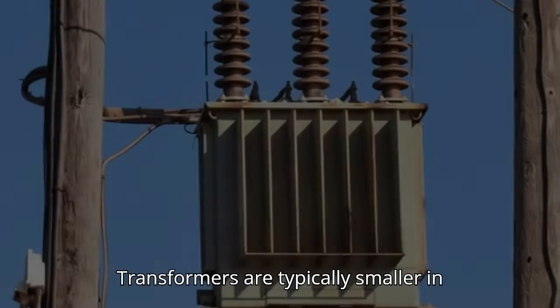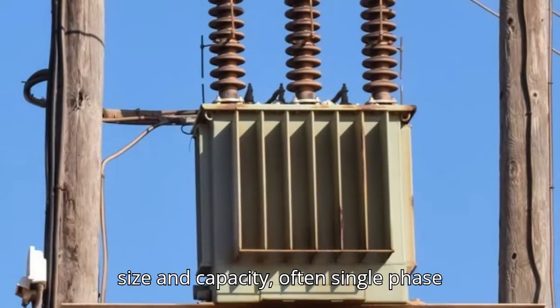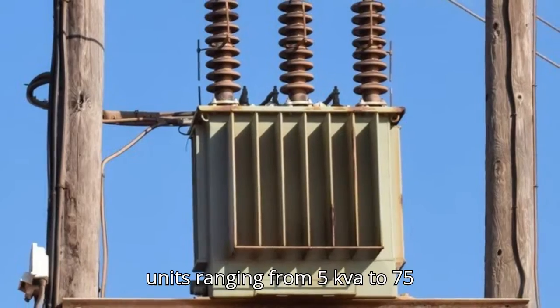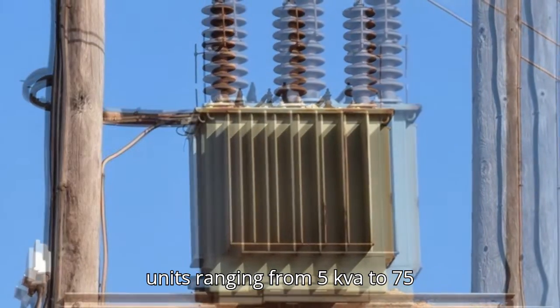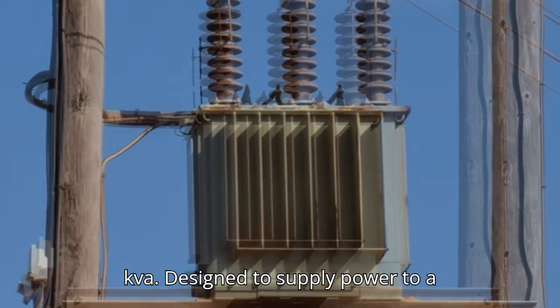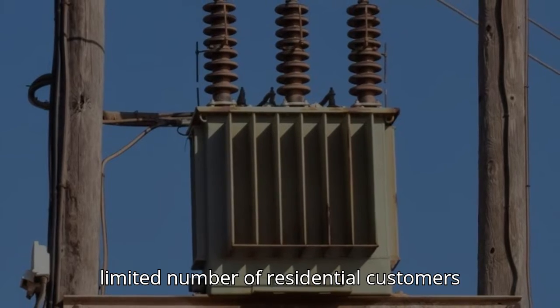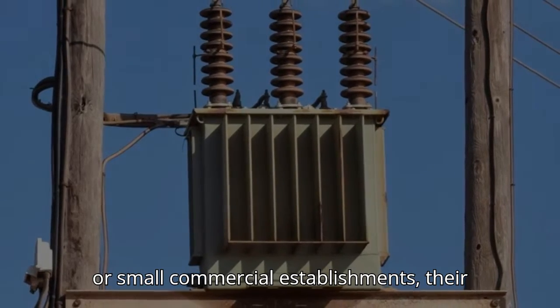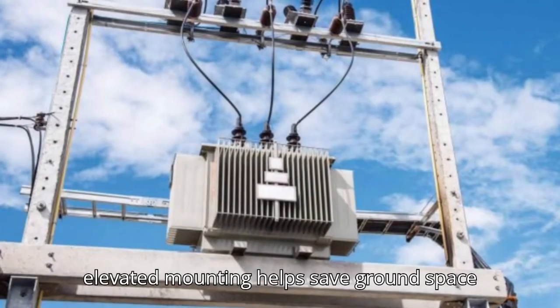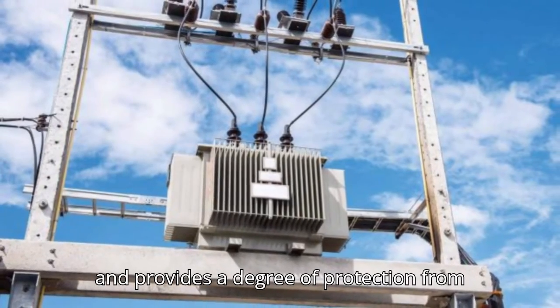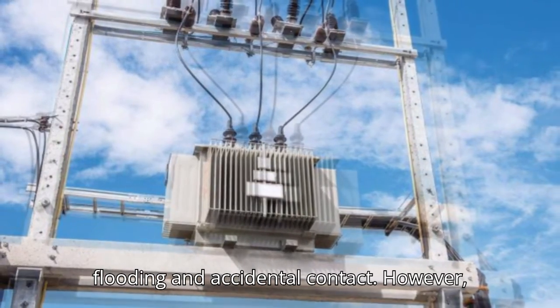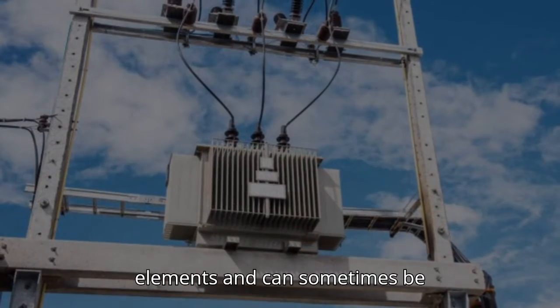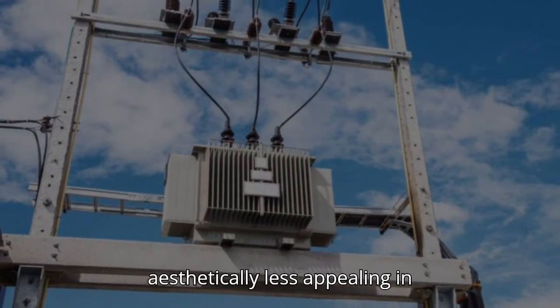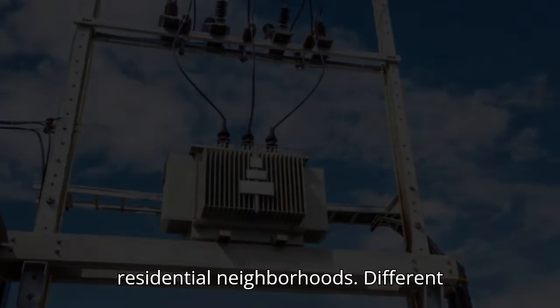These transformers are typically smaller in size and capacity, often single-phase units ranging from 5 kVA to 75 kVA, designed to supply power to a limited number of residential customers or small commercial establishments. Their elevated mounting helps save ground space and provides a degree of protection from flooding and accidental contact. However, they are also more exposed to weather elements and can sometimes be aesthetically less appealing in residential neighborhoods.